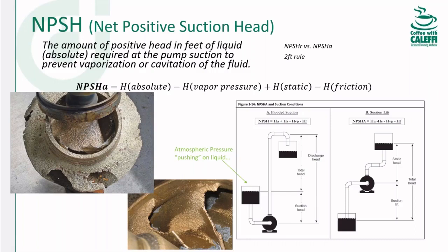I think the important part about NPSH with boosters is that if you've got pressurized water coming from the city, 30, 40, 50, 60 PSI, and it's 60 degrees, you don't have to go through all this. This is especially important when you have a flooded suction coming from a break tank, or you're pulling from below the pump suction. Anytime you're looking at a suction gauge that is almost pegged at zero or below zero, in a vacuum, that's when you really need to go over NPSH. Pressurized water from the city, don't worry about it. Yeah.